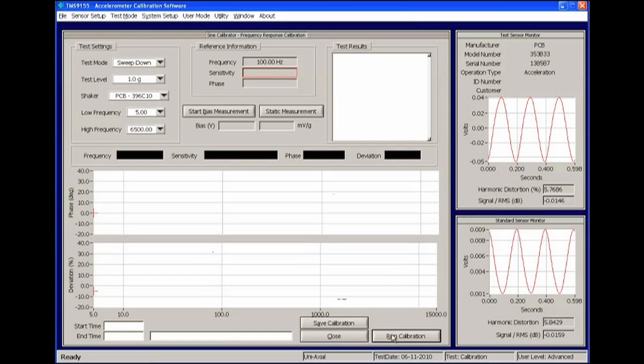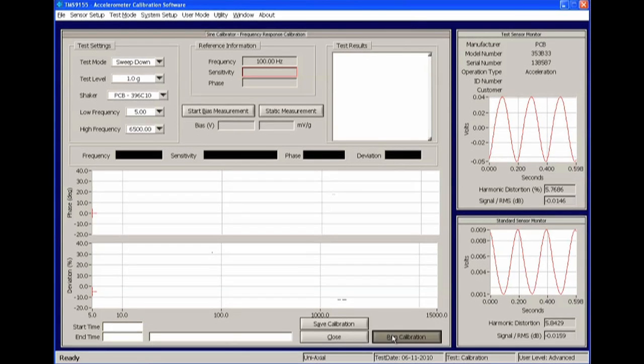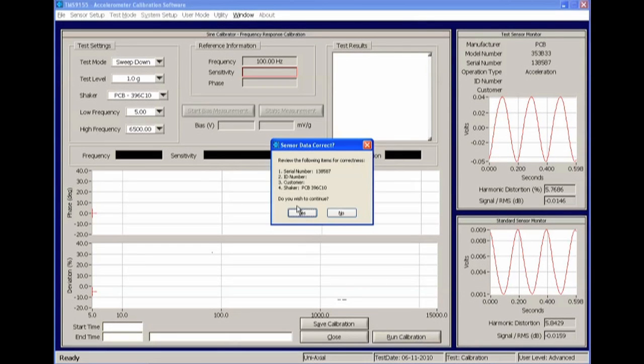Start the calibration by clicking Run Calibration button located in the bottom right corner. Before the test starts, the software will ask you to confirm some of the details of the test you are performing.